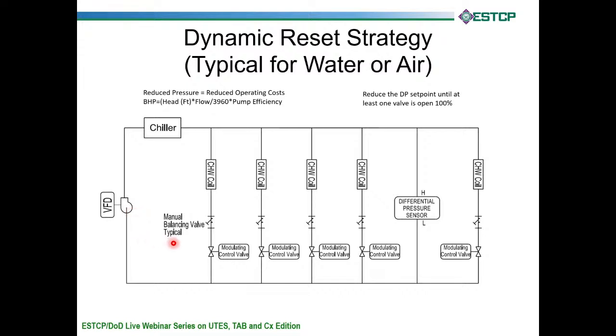What can happen sometimes on chilled water systems is that you can get to a point where all of these valves are throttled and we have no open valves anymore. At that point, our system is really not operating as efficiently as it could. The pump is running too fast. Even though it may be hitting set point, it's running too fast.